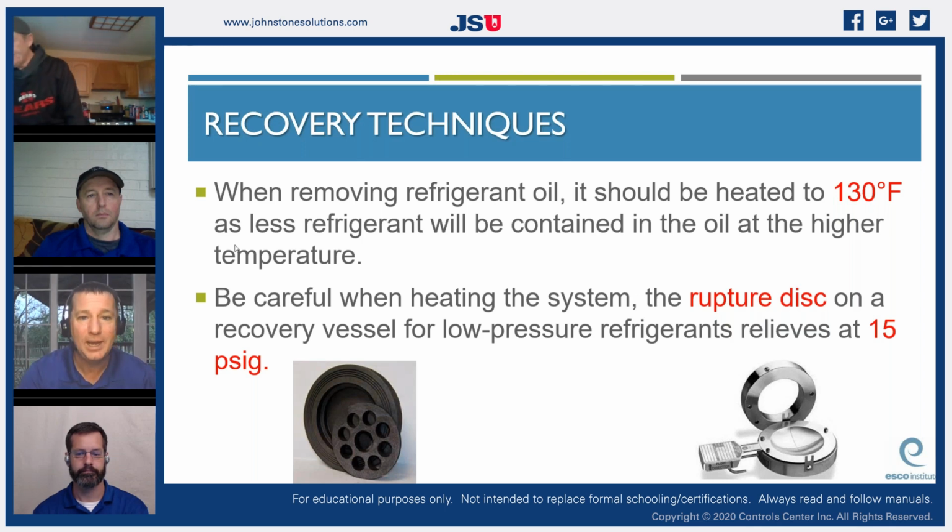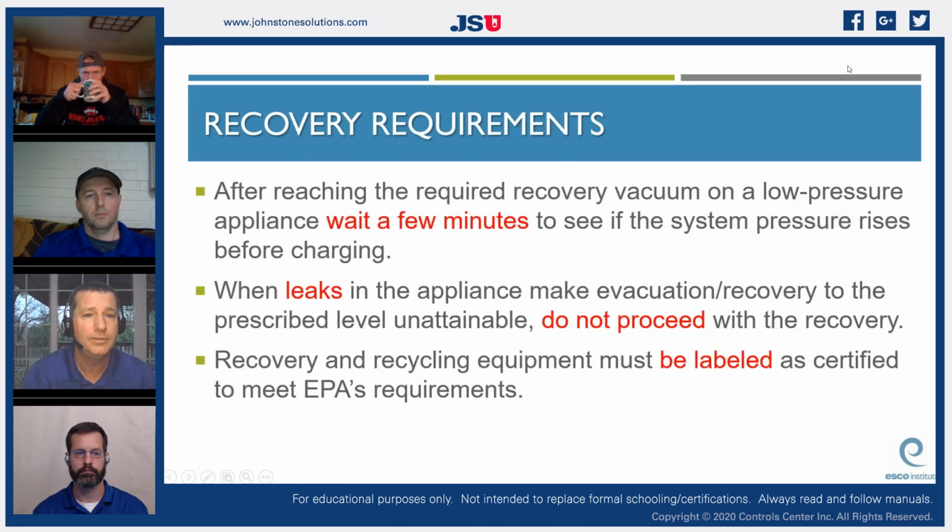So be careful when heating this system, because that rupture disc on the recovery vessel for low pressure refrigerant relieves at 15 PSI. So our recovery vessel, that's typically, a lot of times we basically have a receiver on these pieces of equipment, and that will be the recovery vessel. But if you're using a recovery cylinder, it's still 15 PSI. So you'll see those numbers, 10 PSI on our equipment and 15 on our recovery vessel, are very important numbers to know.